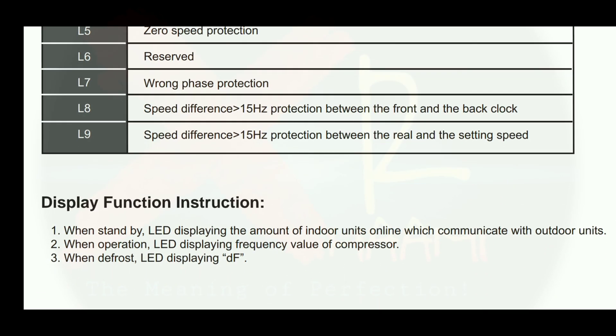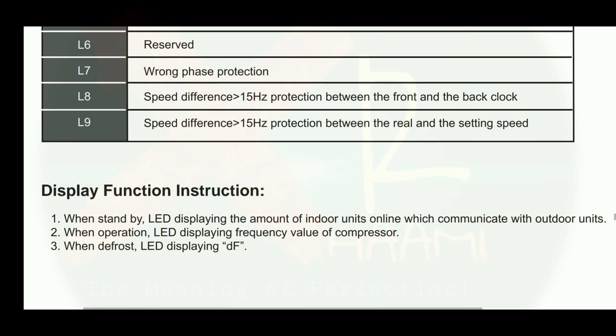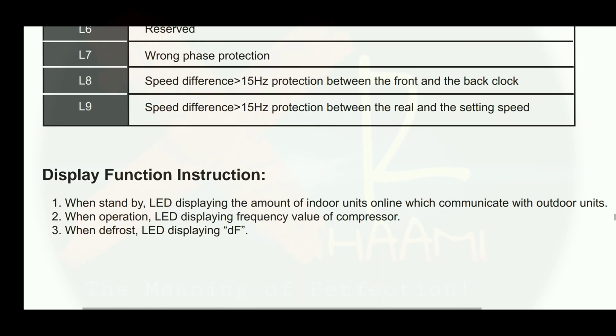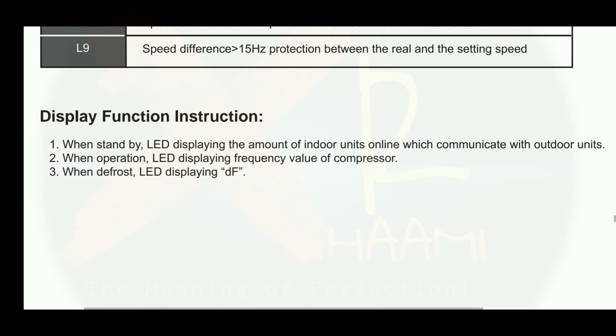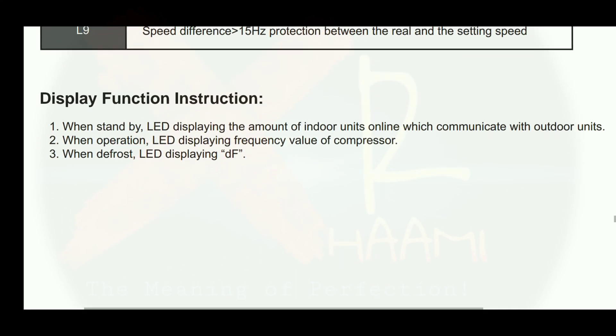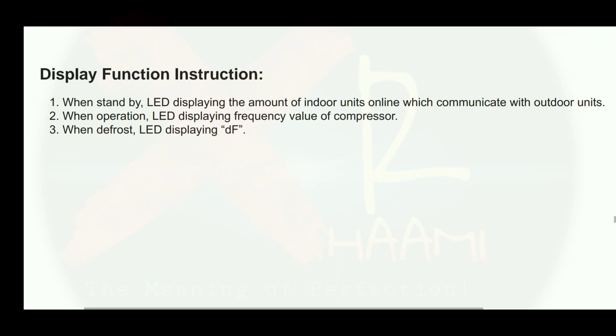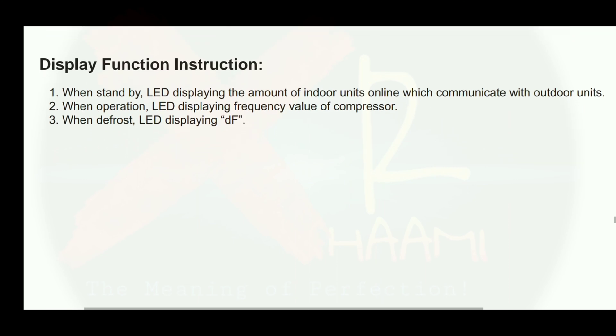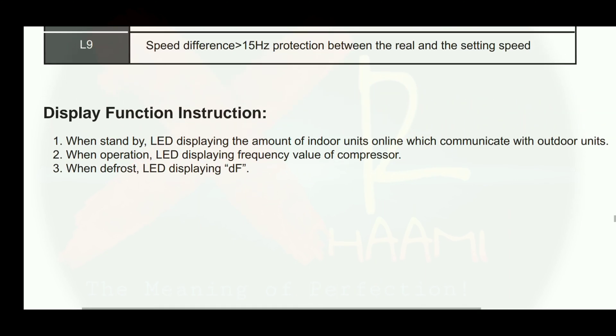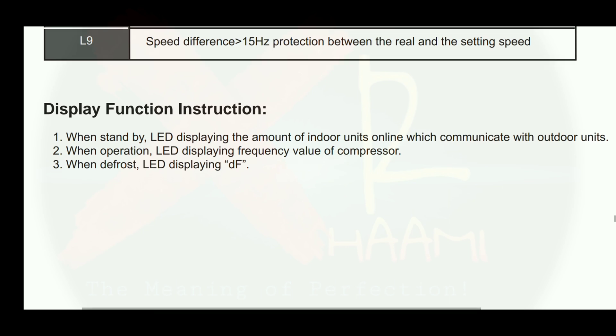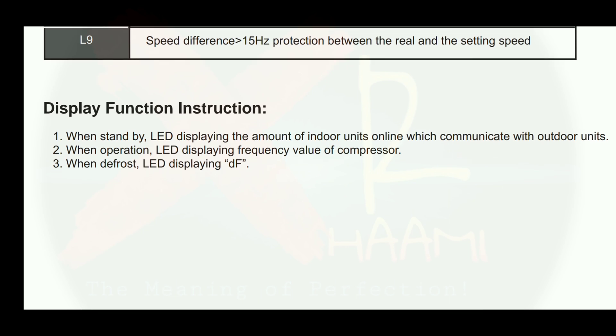The same display function instructions apply here as well. When on standby, the LED displays the number of indoor units online which communicate with outdoor units. When in operation, the LED displays the frequency value of the compressor, and when defrosting, the LED displays DF.